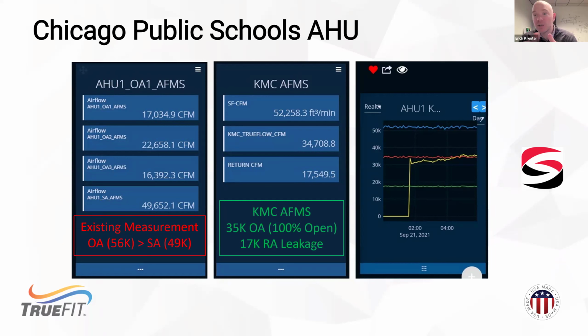So the last chart here, our last picture, is just trend data coming out of our IoT software platform that was on top of this building automation system. We see that there's a total OA again of 52,000. OA is in red, supply or return is in green, and this yellow line is that OA by temps. So we see that when we have proper delta T, we begin calculating what that number is, and we see that the OA by temps match the OA by table, as we would expect.